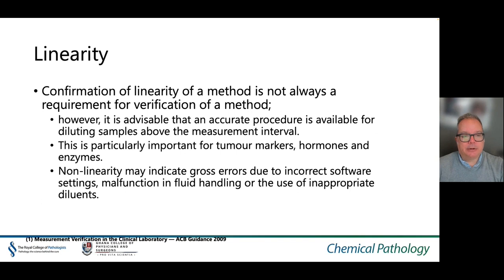Linearity is the confirmation of a method's linear range. Confirmation of linearity is not always a requirement for verification; however, it is advisable that an accurate procedure is available for diluting samples above the measurement interval. This is particularly important for tumour markers, hormones, and enzymes.